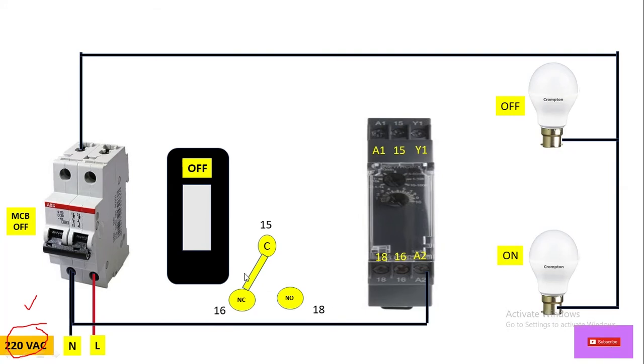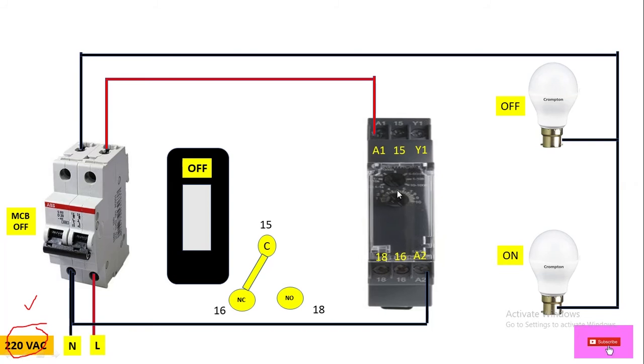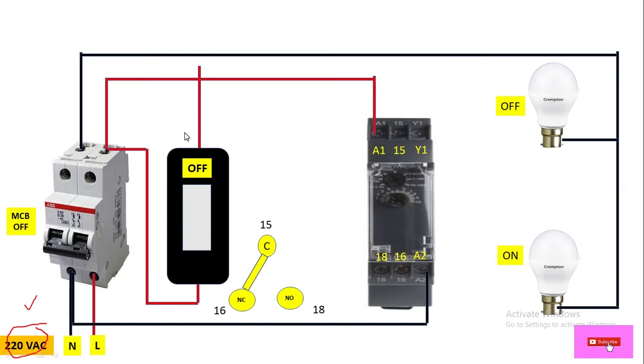For phase wiring, take a red wire from the MCB output terminal and connect it to the A1 terminal. Now the timer has phase at A1 and neutral at A2. For trigger input supply, take a wire to the input terminal of the switch, and from the output terminal of the switch connect it to the Y1 terminal, which is the trigger input terminal.